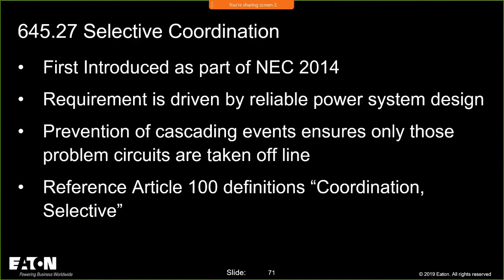645. Now, selective coordination in 645 was introduced in 2014, and it's again driven by reliability. Selective coordination is focused on reliable power distribution systems and making sure that the downstream device trips before the upstream device does. In information technology equipment and those applications, they care a lot about making sure they don't take parts of their distribution system down without due cause. So they care a lot about that.